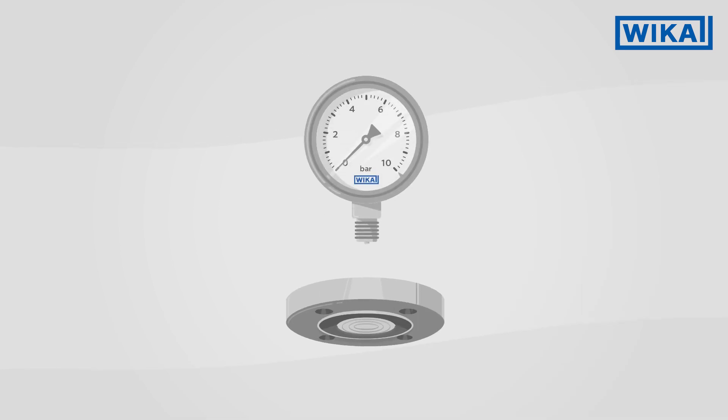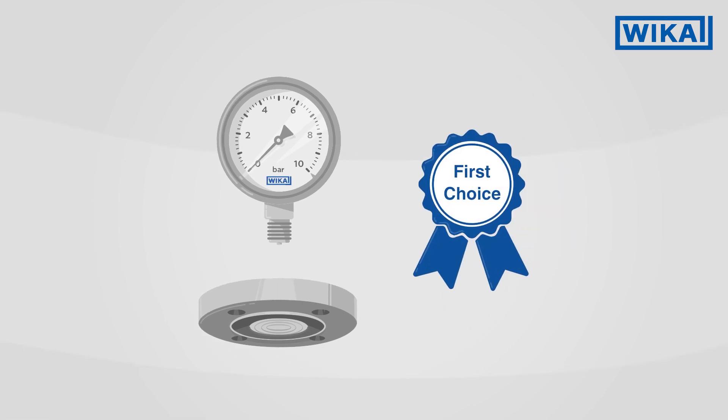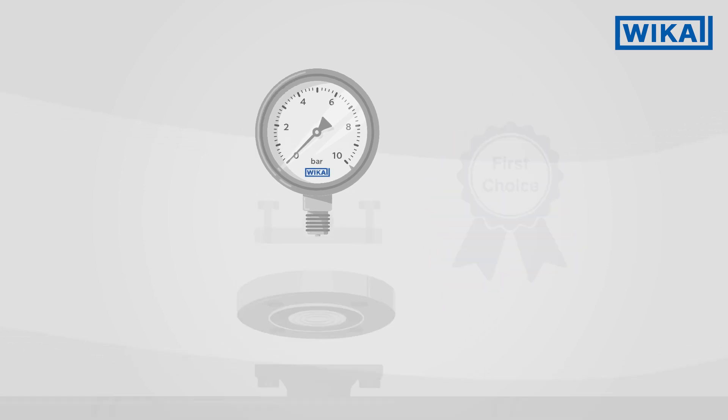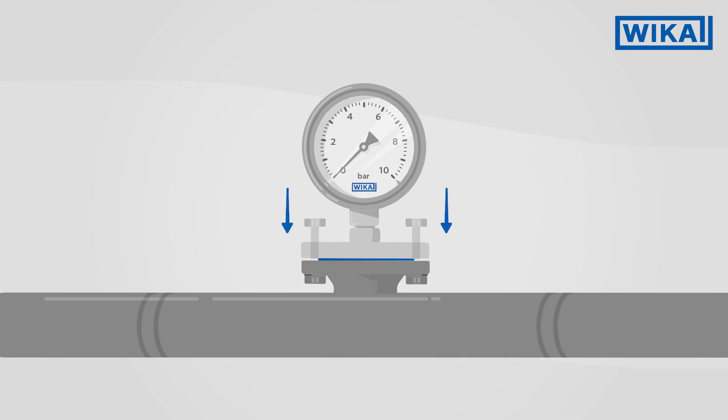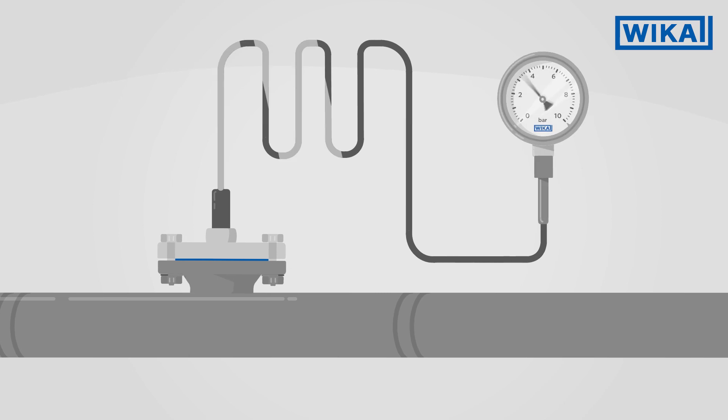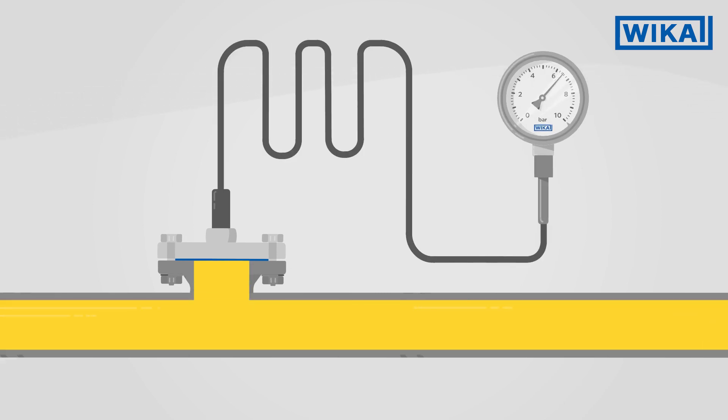Diaphragm seals with flange connection are multipurpose connections and the ones most frequently used worldwide. Flange connections offer numerous advantages. Their mounting prevents the capillary line or the already connected cable from twisting. The larger pipe diameter also allows for highly viscous and flocculent media.